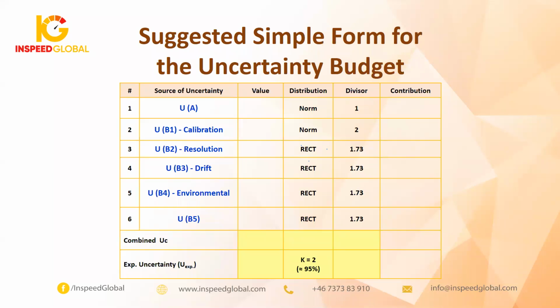For type B, you can go directly to the calibration certificate to get the uncertainty of your equipment, and directly divide by 2 and mention it in the contribution, the last column. For resolution, you get the smallest value you can read in your equipment, divide by 2, and after that divide by 1.73. For drift, you can get the difference between the uncertainty of the 2 calibration certificates and divide by 1.73. As you see, my dear, you have a lot of results, but how to combine all these results to get the final result of uncertainty? As you see, we have 2 others at the bottom: combined uncertainty and expanded uncertainty.